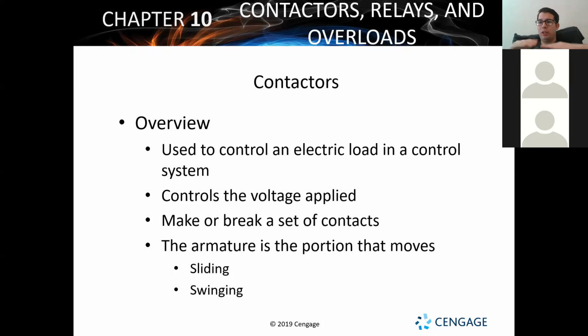If I have a switch and it's open, and let's say my ceiling fan was off, and I was to read that switch, I would check one side of the switch and the other side. I would check power coming in and then power going out to my light. Because there's a break in between the two, it's just like when there was a load. Now there's a difference. This side has nothing going on. There's no power getting to my ceiling fan. And this side has got power just waiting to go right to that fan. So that difference in voltage allows you to read on an open switch 120 volts.